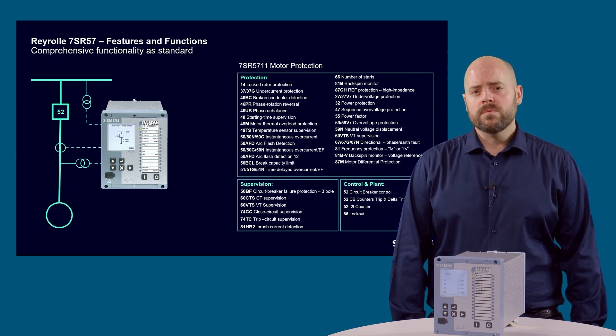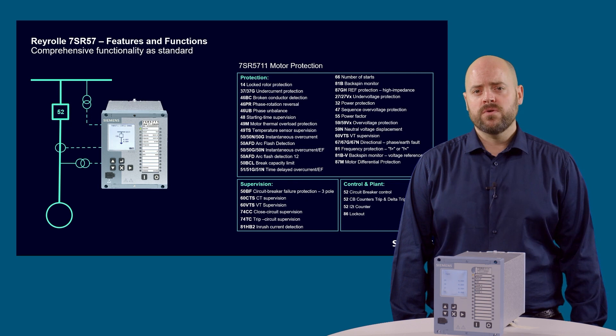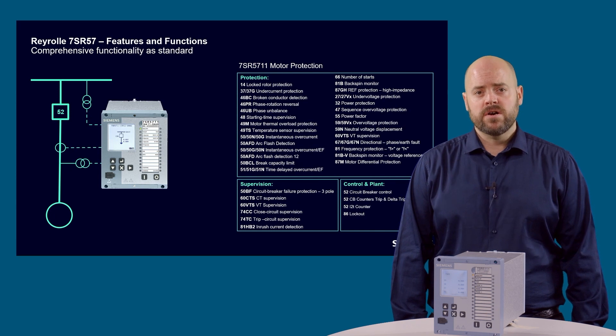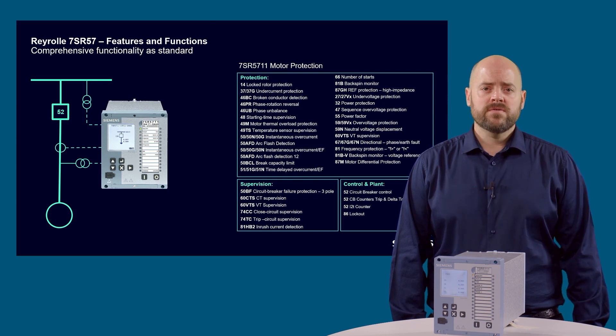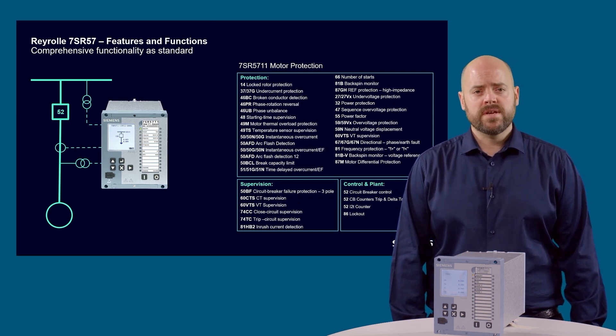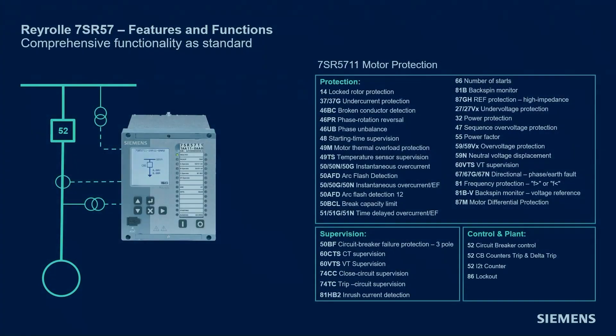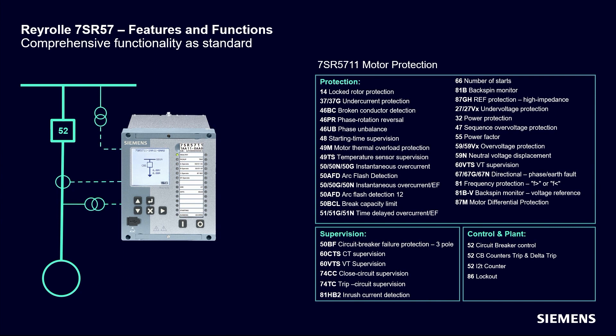The 7SR5711 motor protection device has 4 CT inputs and 4 VT inputs, which allow additional functionality over the 7SR5710. Also available are 7SR5721 devices with 8 CT inputs; devices with 8 CTs can provide motor differential protection. With the addition of the voltage inputs, the device has all associated protection functions including under-voltage protection function 27, which can be used to disconnect the motor in the event of low terminal voltage, as well as power flow monitoring function 32 and comprehensive current and voltage-based instrumentation.